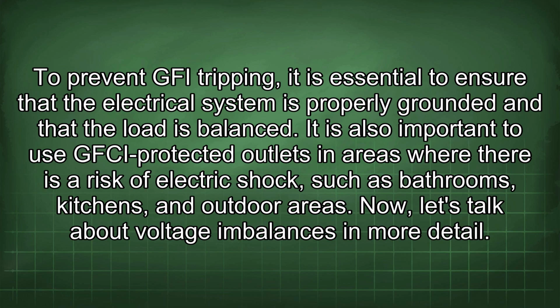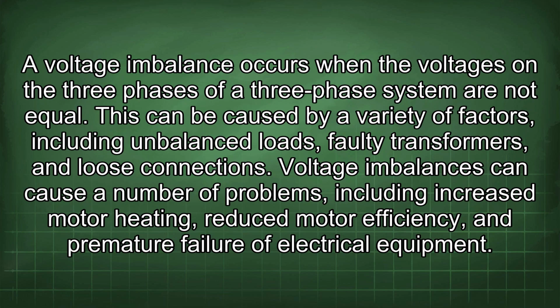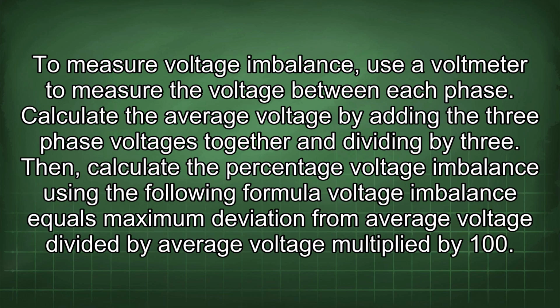Now let's talk about voltage imbalances in more detail. A voltage imbalance occurs when the voltages on the three phases of a three-phase system are not equal. This can be caused by a variety of factors, including unbalanced loads, faulty transformers, and loose connections. Voltage imbalances can cause a number of problems, including increased motor heating, reduced motor efficiency, and premature failure of electrical equipment. To measure voltage imbalance, use a voltmeter to measure the voltage between each phase.